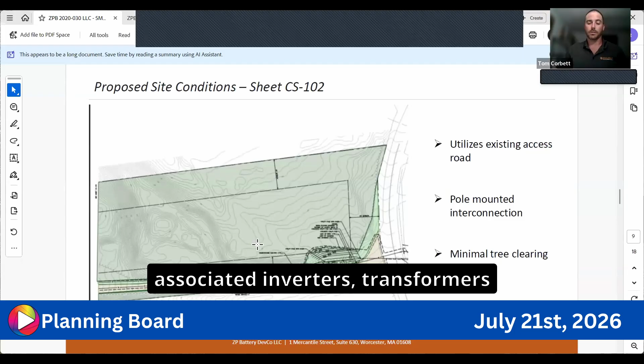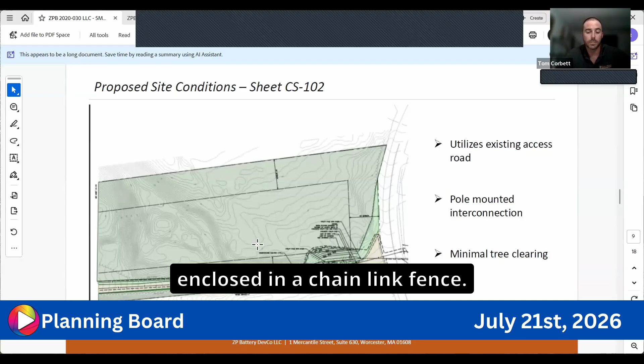The proposed facility includes the installation of 5 battery energy storage containers, along with the associated inverters, transformers, and other electrical equipment for the project. The battery containers will be installed on concrete pads and surrounded by a secondary containment system below grade. Ground mounted equipment will all be installed on concrete pads. The ground surface immediately surrounding the ESS will be gravel and enclosed in a chain link fence.